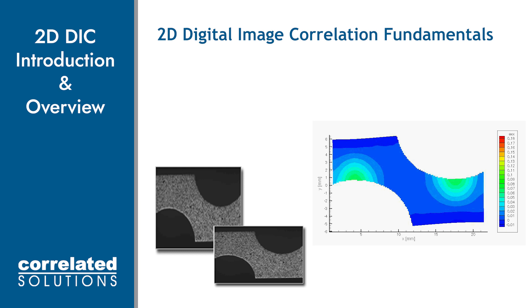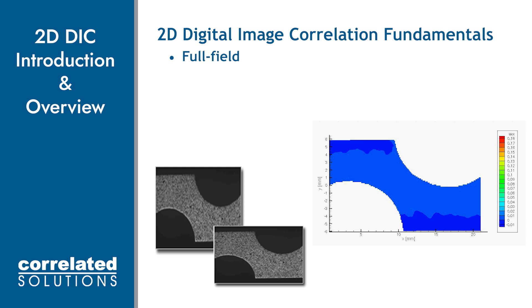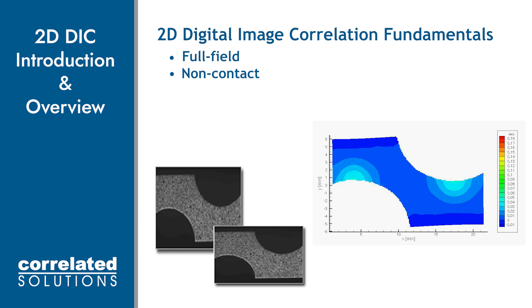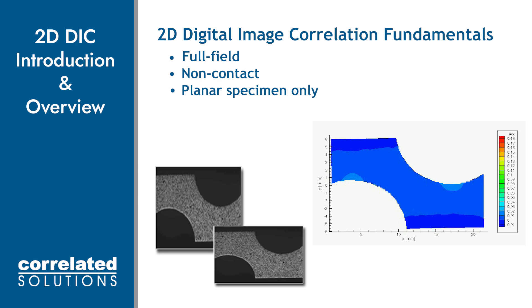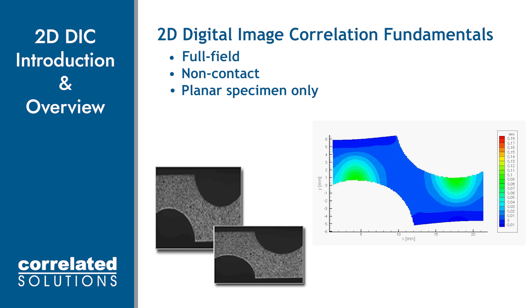2D digital image correlation, or DIC, uses images from one camera to obtain full field shape, deformation, and strain data. It is non-contact. While 3D DIC allows for any shape and any motion, for 2D DIC we have only 2D information from one camera, so the specimen must be flat and planar to the imaging sensor. Out-of-plane motion will cause a bias in our 2D data, so motion towards or away from the camera should not occur for 2D DIC.